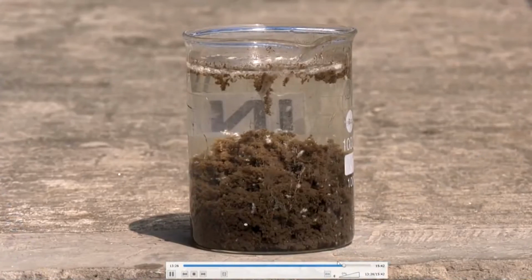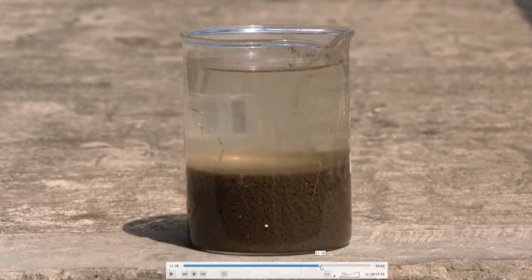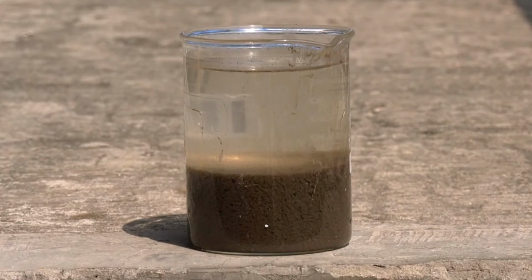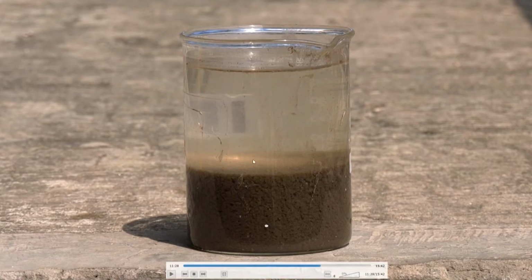So, after the sequential batch reactor, the last stage was decanting. You are not going to pump the water out, you decant the water gently, right. You do not want to disturb the settled sludge which is being pumped out. So what do we have? We still have some suspended solids, as you can see, even after the sludge has settled out, but again this is only 30 seconds. Typically we give 1 hour or so, and the height is obviously 2 to 3 centimeters. So you still have some suspended solids, but typically it will be much clearer after I let it stay for 1 hour.